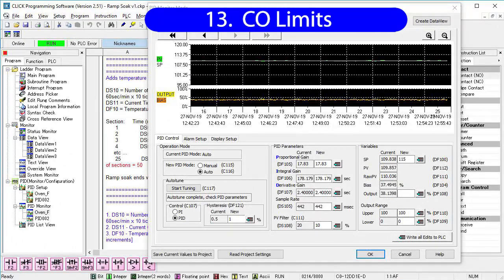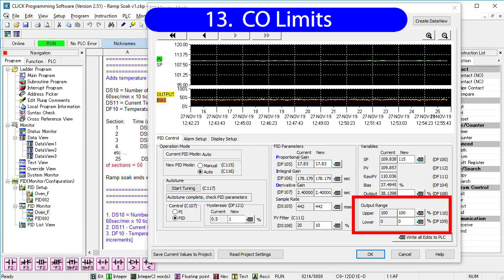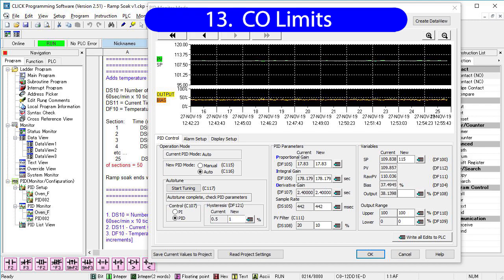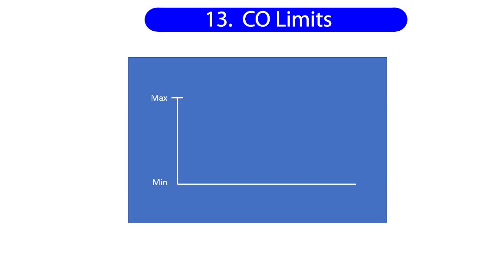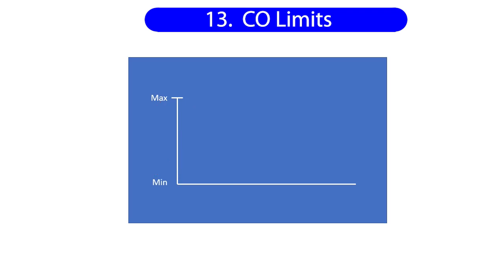You can limit the magnitude of the control output. Maybe you don't want your system to be able to go to the max possible value for safety reasons or to protect your machine. You can set that limit on both the high and the low end. And that works regardless so it will also prevent auto-tune from driving the system too hard. Just understand that this isn't rescaling the output – it's cutting off portions of the output range.